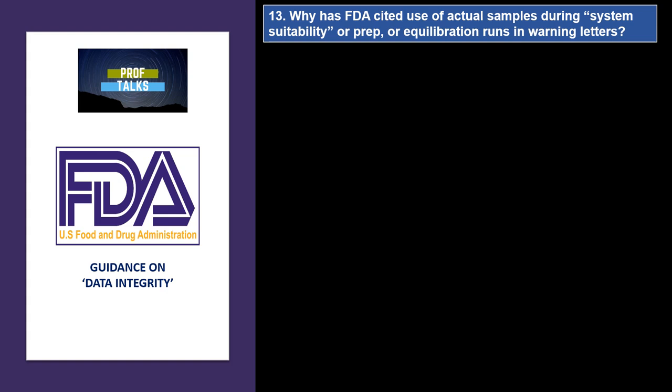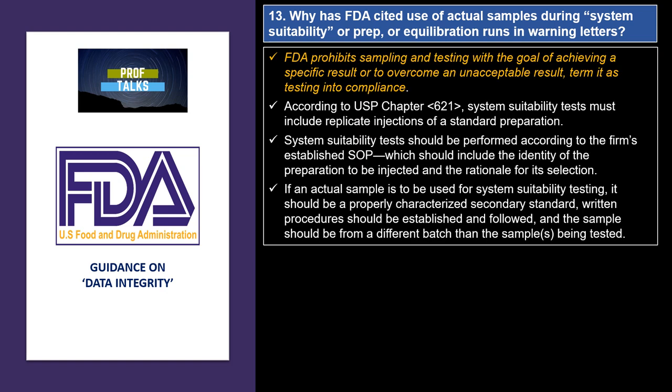Why has FDA cited the use of actual samples during system suitability or equilibration runs in warning letters? FDA terms this as testing into compliance and prohibits sampling and testing with the goal of achieving a specific result. According to USP Chapter 621, system suitability tests must be a replicate injection of a standard preparation. The standard preparation should be defined in the SOP and the rationale for its selection documented. If an actual sample is used for system suitability, it should be a properly characterized secondary standard, a procedure should be available for it, and it should be from a different batch than the one being tested.